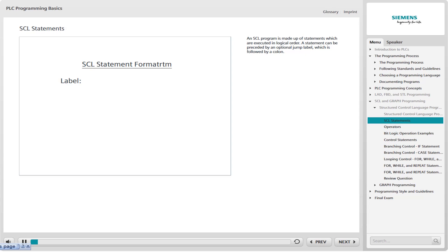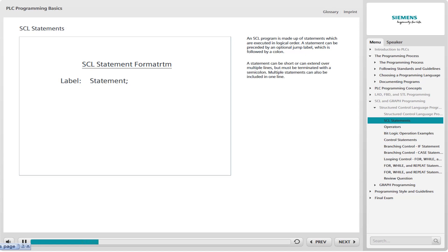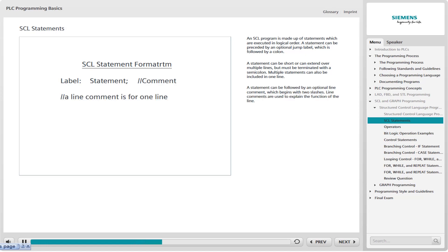An SCL program is made up of statements which are executed in logical order. A statement can be preceded by an optional jump label, which is followed by a colon. A statement can be short or can extend over multiple lines, but must be terminated with a semicolon. Multiple statements can also be included in one line. A statement can be followed by an optional line comment, which begins with two slashes. Line comments are used to explain the function of the line.